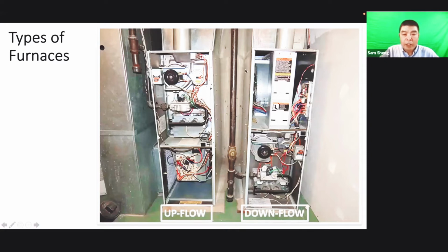And like you said, for the gas train here, normally for a new furnace the gas valve is what we call a 4-in-1. A very old furnace has 4 different parts, but all these 4 different parts have the same function as this one gas valve now.